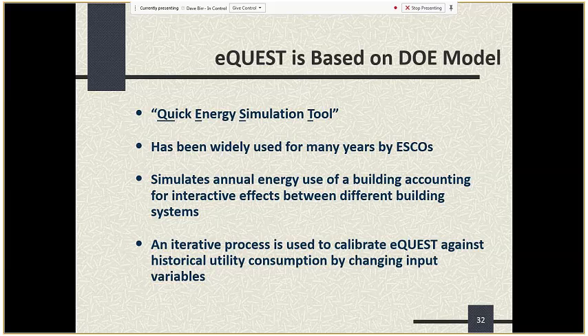Usually with eQuest, you're doing a certain amount of calibration where you're looking at historical utility data, how you modeled the building with your user-defined inputs and the default inputs, and then running a model to see if it can produce the historical utility consumption. If it does, within a reasonable accuracy, say plus or minus 5 or 10%, you know you've got a model that's giving you a reasonable picture of how the building performs.